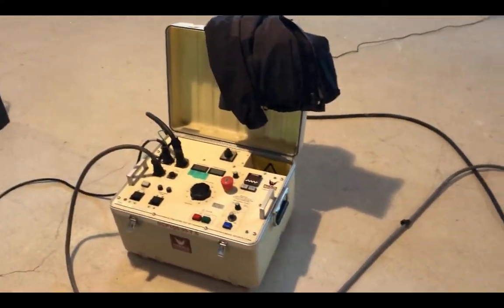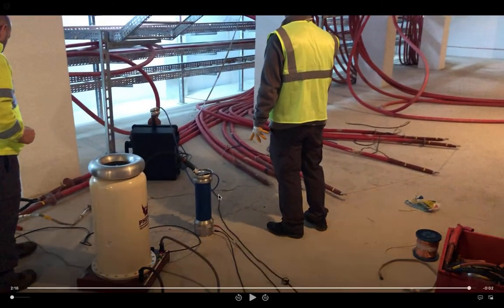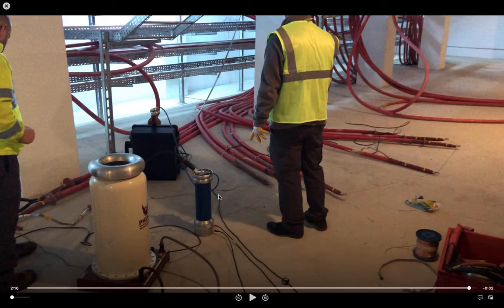After connecting to this unit, we are just showing you the connection of the control unit, and this is the overall setup how we have done this test. I hope you've understood how the setup goes. I also hope that now you understand a little bit closer how this is done. It's demystified a little bit. And once again, this is an offline test in comparison to an online test. Online test would be done while the cables would be transmitting power, and in that case we would be just using the HFCT since in that case we cannot touch the conductor itself. So in this case we generate onto a sensor directly which is connected to the cable. We have two sensors and we are connected to the acquisition unit.